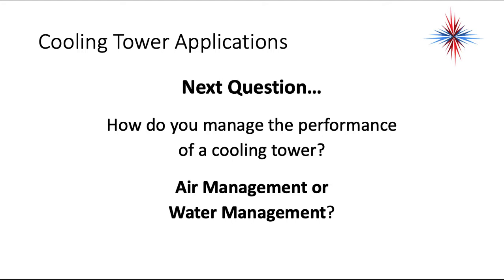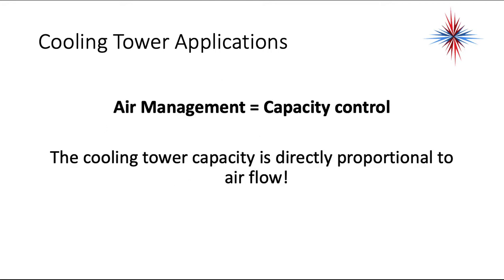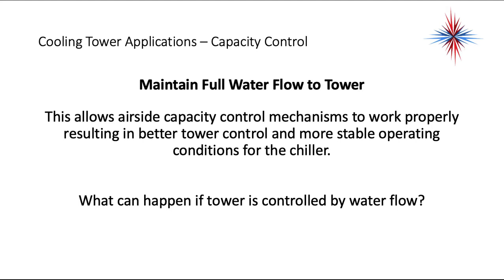So how do we manage the performance of a cooling tower — do we use air management or water management? Both are possible. Air management equals capacity control; the cooling tower capacity is directly proportional to air flow — more air flow, more capacity. The other way is to maintain full water flow to the tower, which allows air-side capacity control mechanisms to work properly, resulting in better tower control and more stable operating conditions for the chillers.